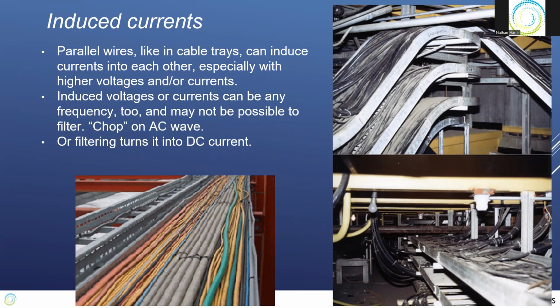Like we had this control company I was working at back in Illinois. We connected the PC to the controller on the Modbus port. And at the time, our PCs were only plug-in AC powered, on a cart. They weren't laptops back then. And so when we plugged the Modbus port in, we grounded the switchgear through the Modbus port and blew the Modbus port out on the controller.